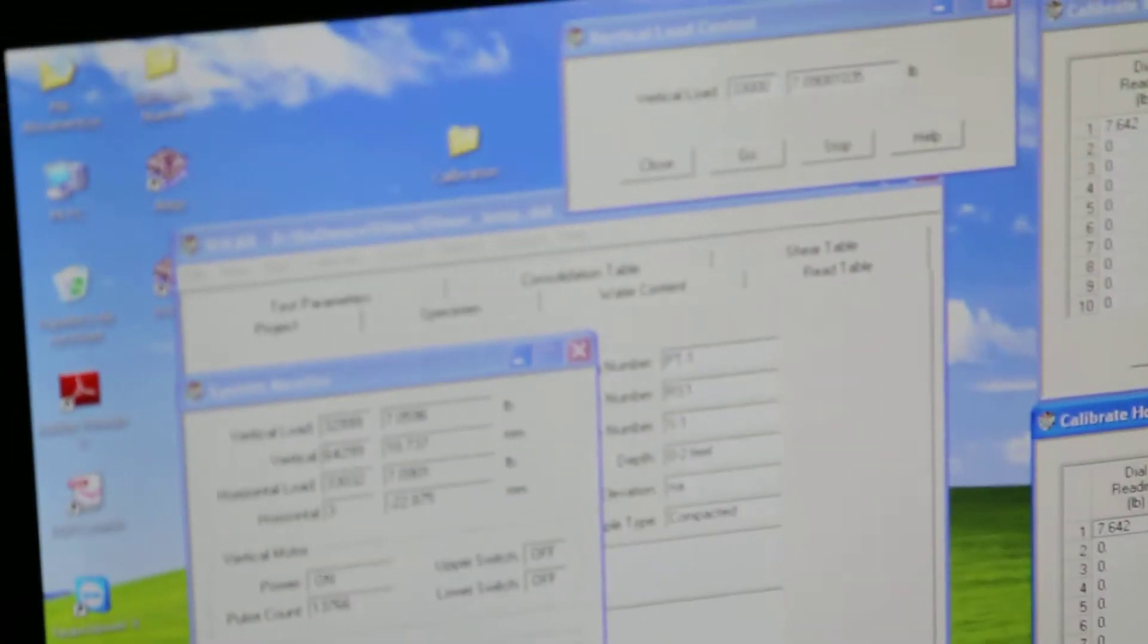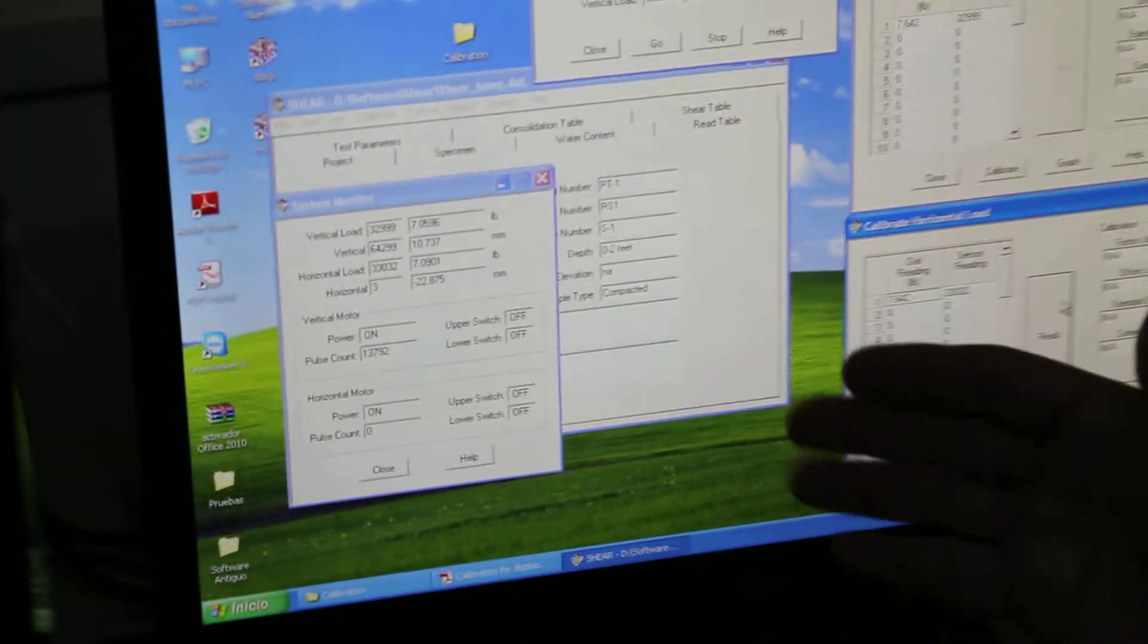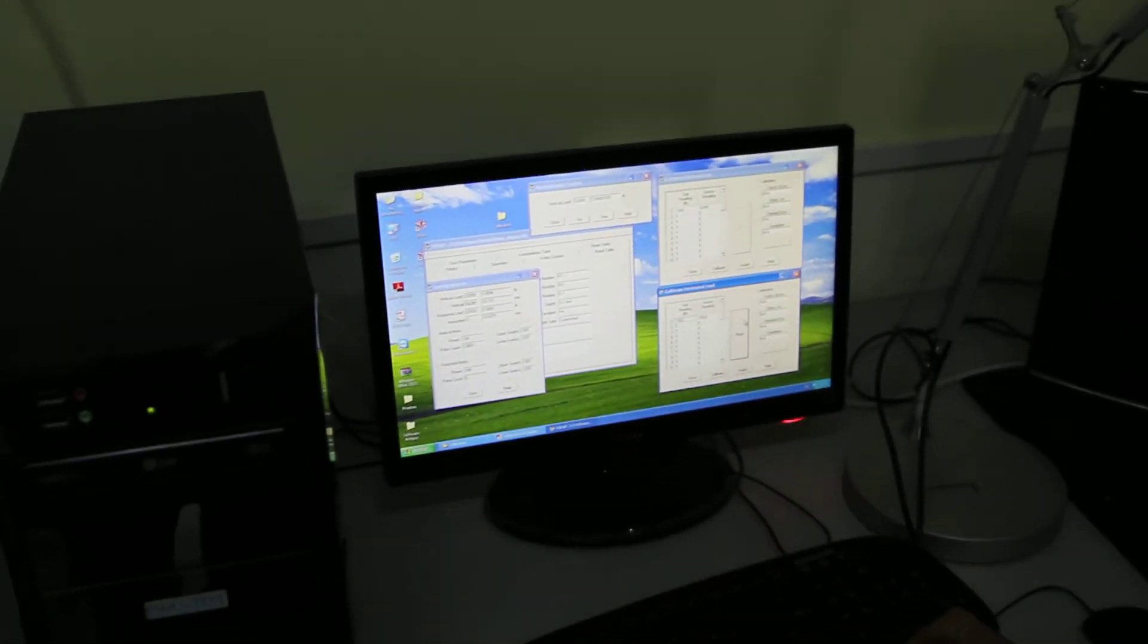I will continue by increasing my target counts by 2,000 counts, so my next one will be 35, then 37, then 39, then 41, and so on so forth. So I can cover the range of my two load cells, and then at the end I'll have a complete table. I will click on calibrate for both of them and I got my calibration factor. Then I hit save and it will automatically save it, and that would be the end of my calibration for my direct shear.